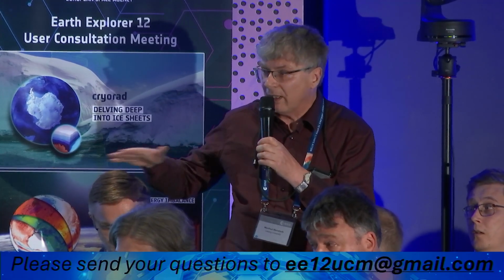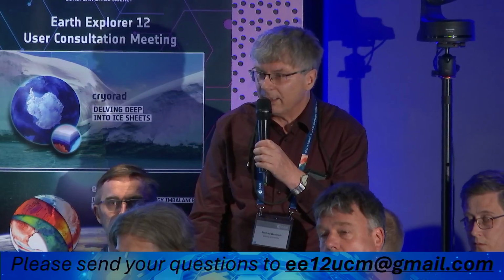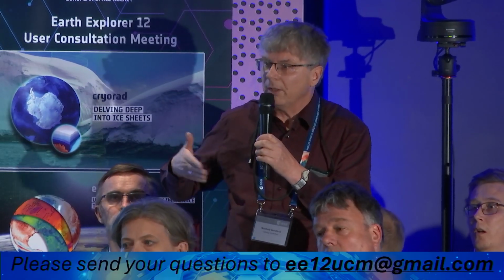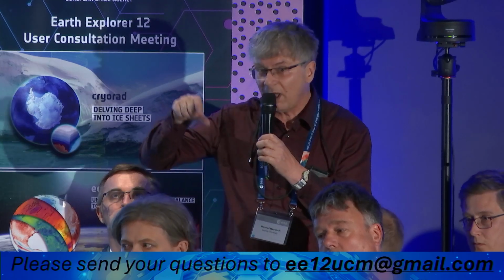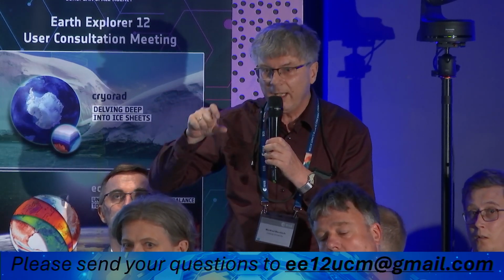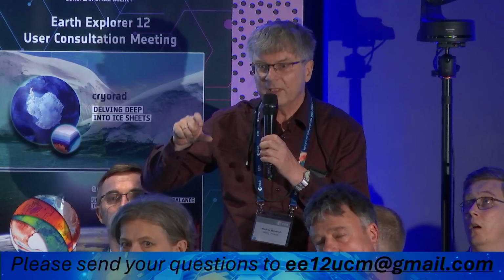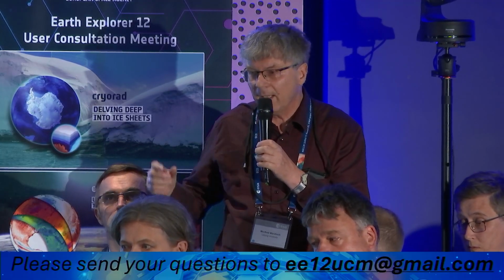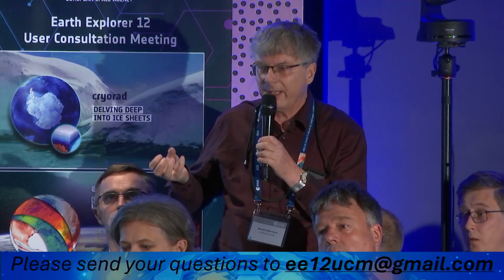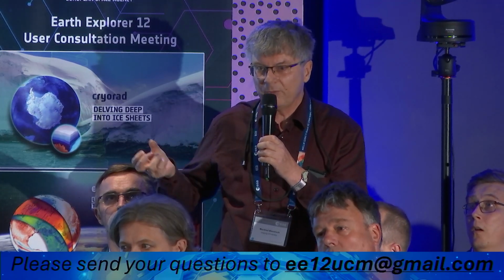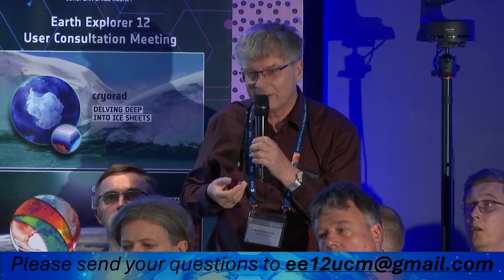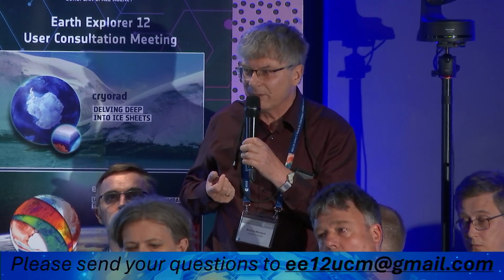If you don't use this wide field of view, then you have much more uncertainties in the flux measurements. And we start from the flux measurements. We need the high accuracy for the flux measurements from the very beginning. Otherwise, we are lost. We cannot resolve this 1 watt per meter squared imbalance. And I would also like to mention, it's also a first principle measurement. If we use these bolometric instrumentation, then we wouldn't need a calibration in principle. And that makes a difference.